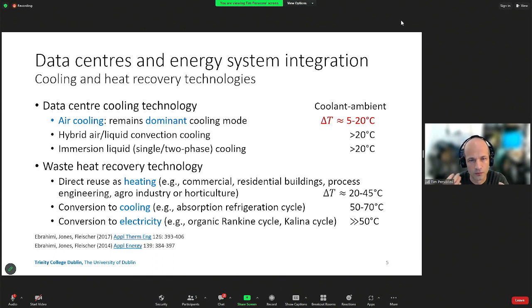In terms of coolant to be used for waste heat recovery, that's basically useless energy, right? So we need to be able to increase that delta T. And that's where other technologies like liquid cooling, hybrid air-liquid cooling or immersion cooling could come in, to increase that delta T and be able to do something more with that waste heat.